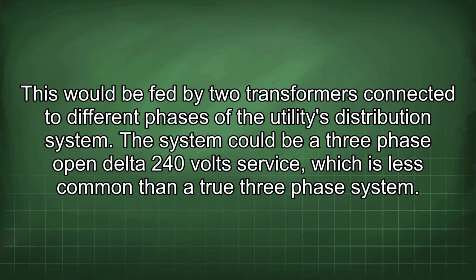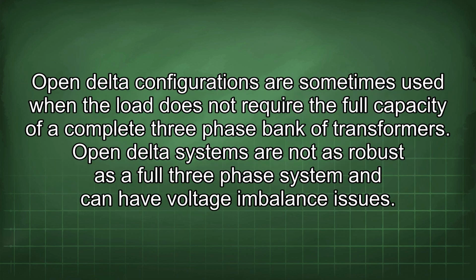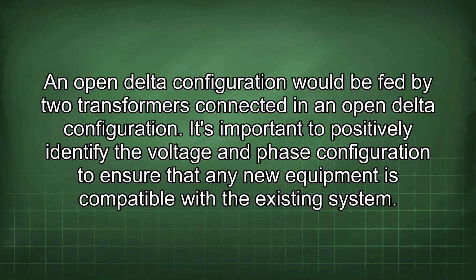The system could be a three-phase open delta 240 volt service, which is less common than a true three-phase system. Open delta configurations are sometimes used when the load does not require the full capacity of a complete three-phase bank of transformers. Open delta systems are not as robust as a full three-phase system and can have voltage imbalance issues. An open delta configuration would be fed by two transformers connected in an open delta configuration.